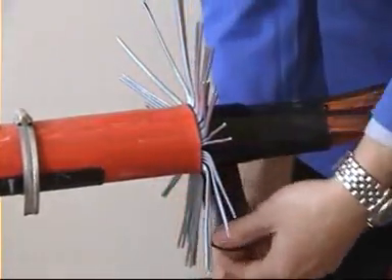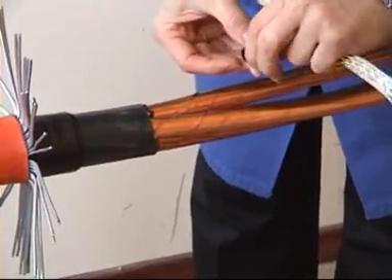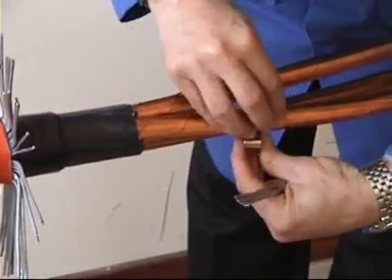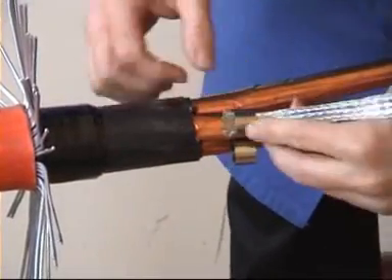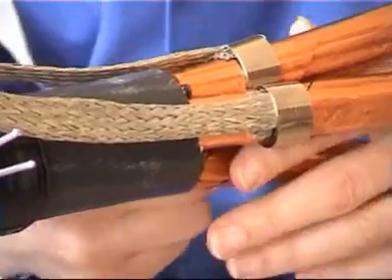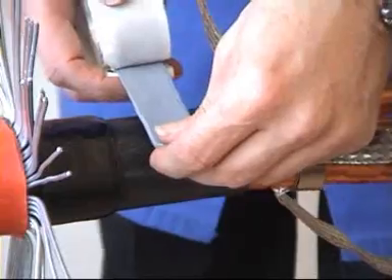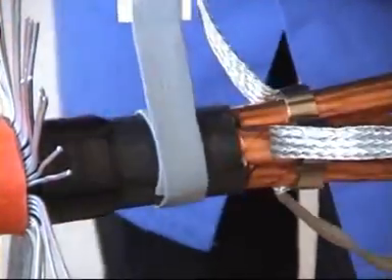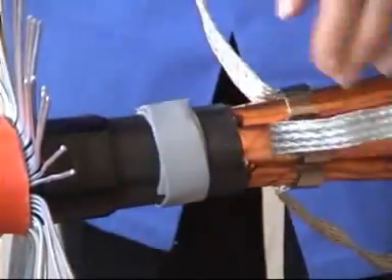Apply a length of the black mastic tape beneath the armours. This will act as a moisture block later on. Take the XLP earthing kit, and with the constant force roll springs, secure the earth braids to each core. Apply a length of grey mastic tape, and bend the earth braids down onto this tape.